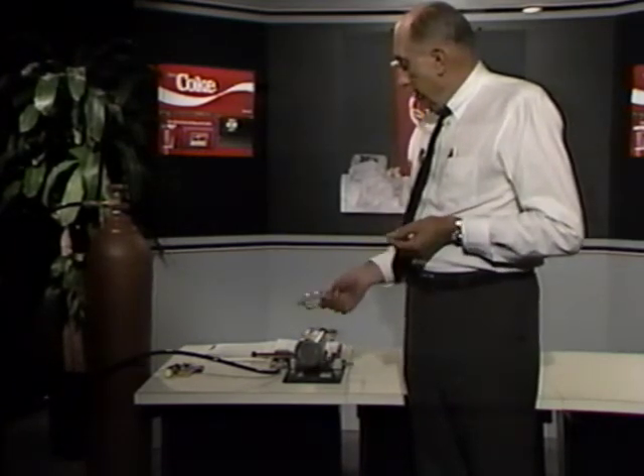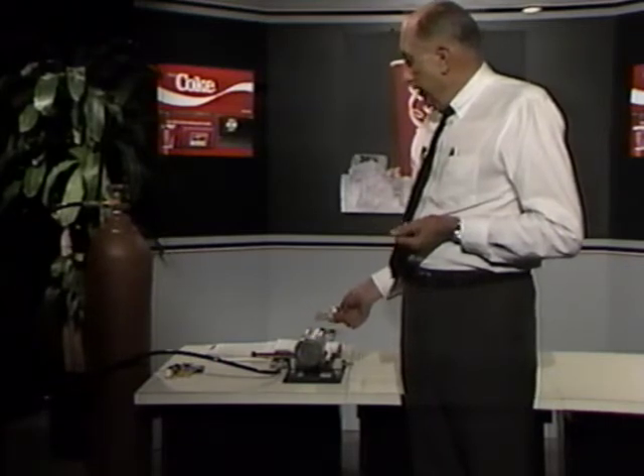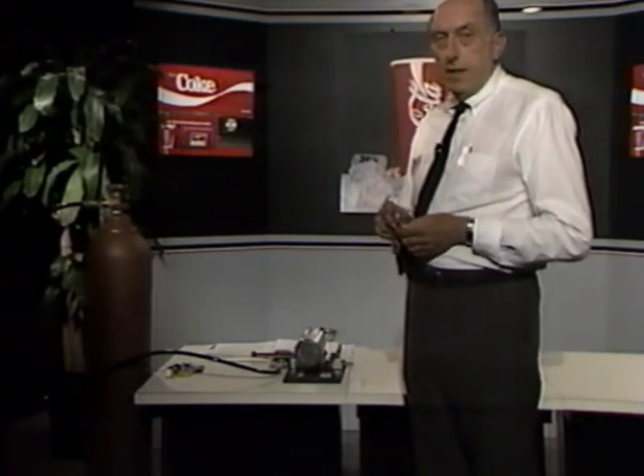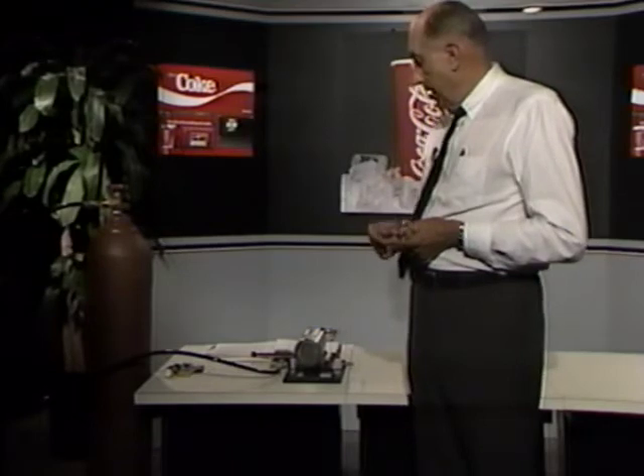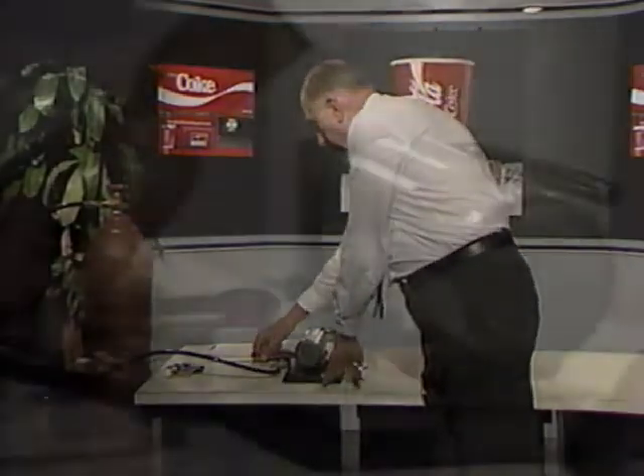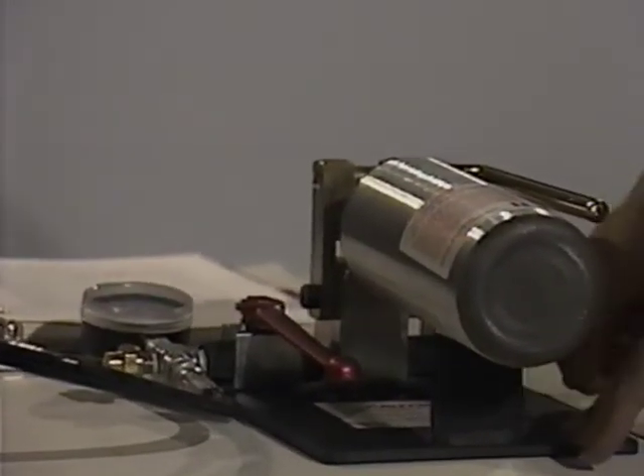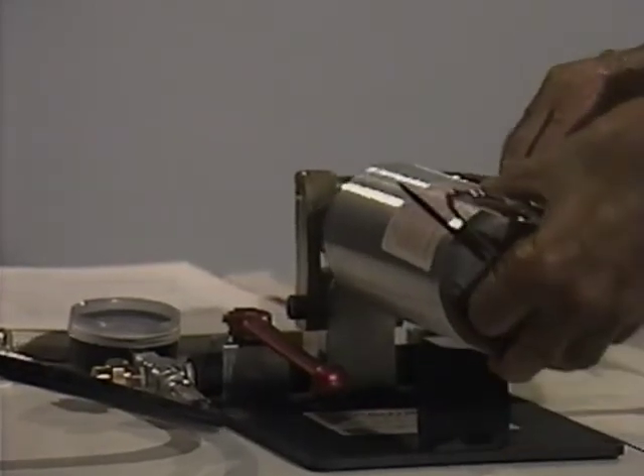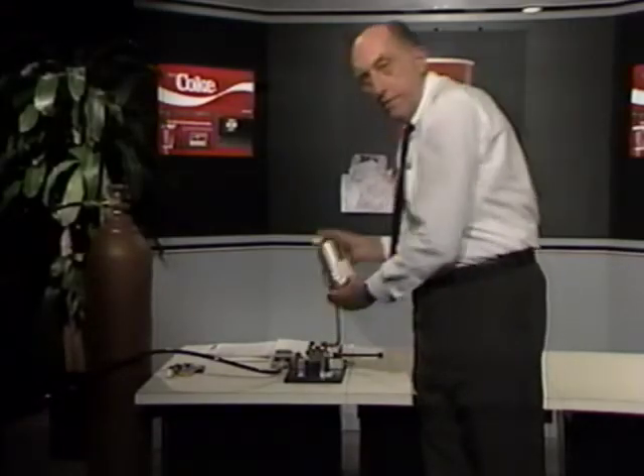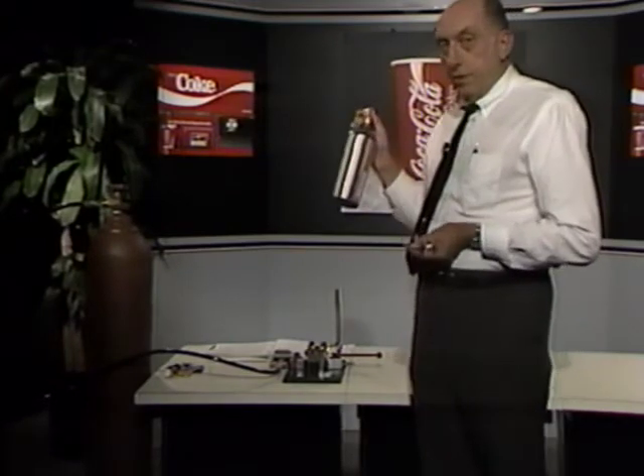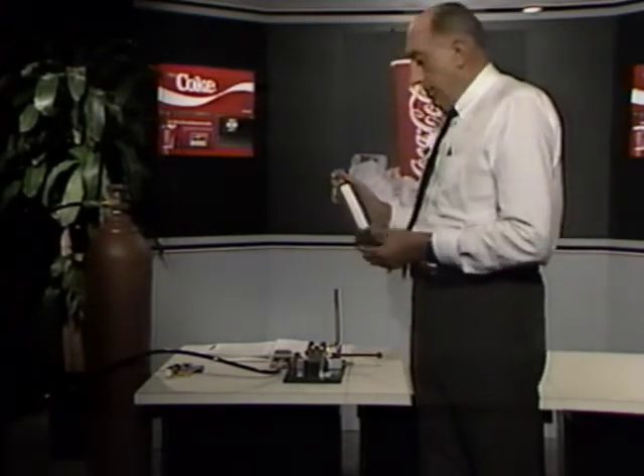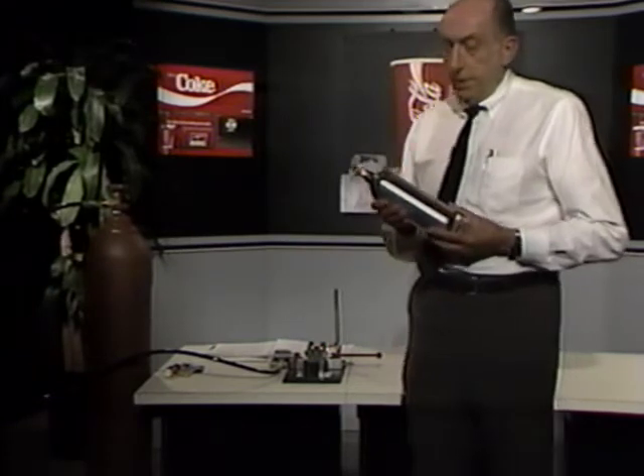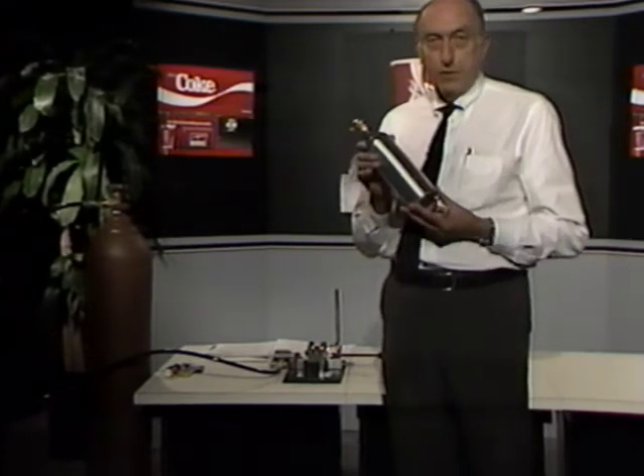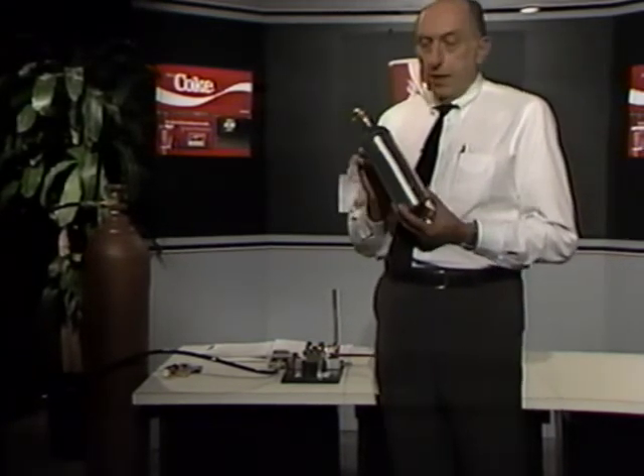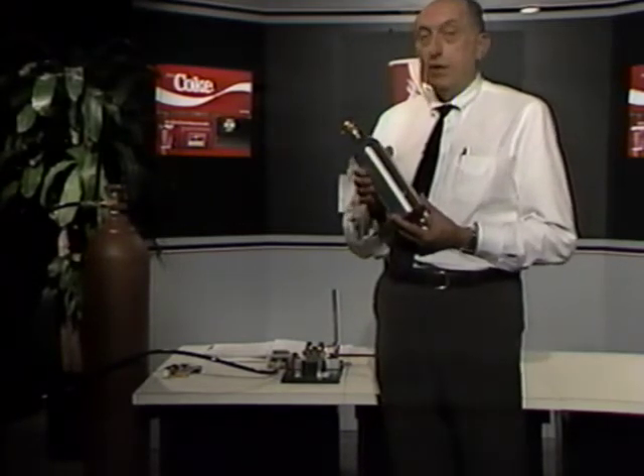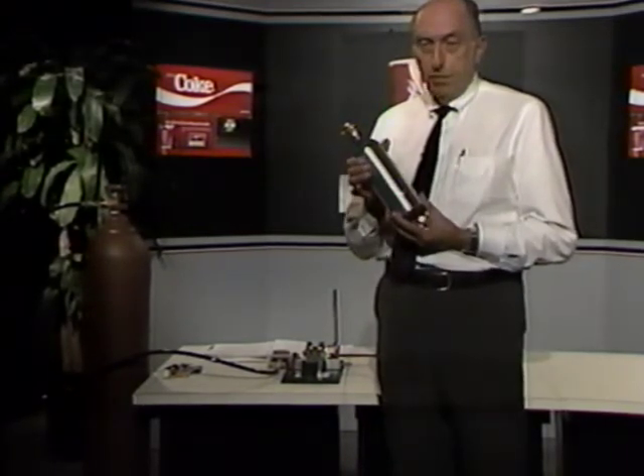When you hear the noise stop, that indicates that the cylinder is about as full as it's going to get. So we'll shut off the inlet valve, vent the cylinder, and then we want to be sure to check the weight. The reason it's important to check the weight on the cylinder and not exceed 3 pounds 5 ounces total weight is because this small cylinder is now also charged with liquid CO2.